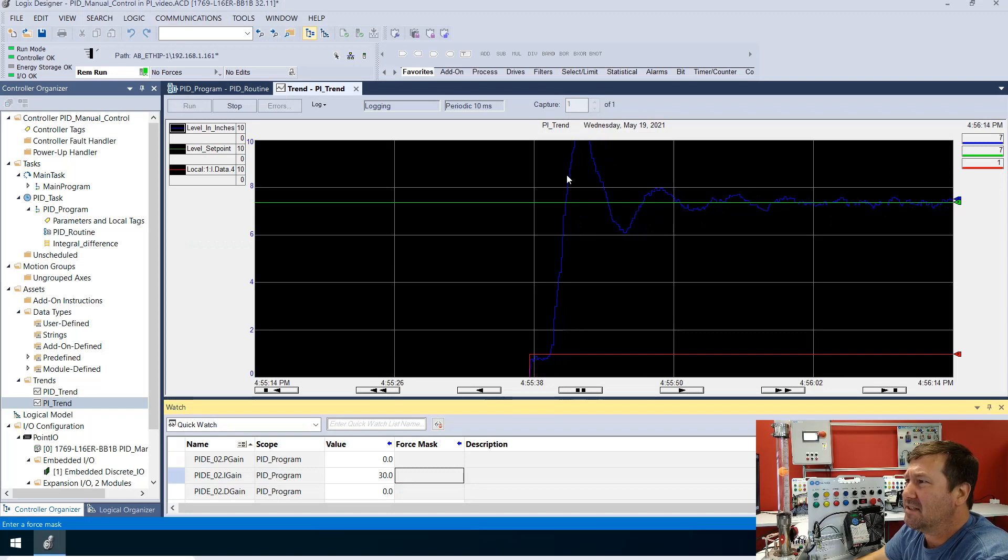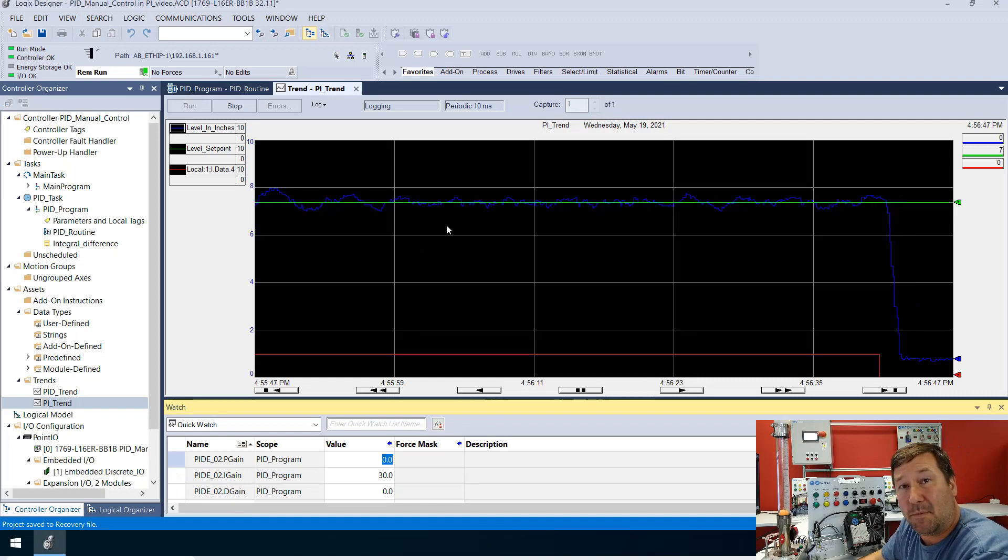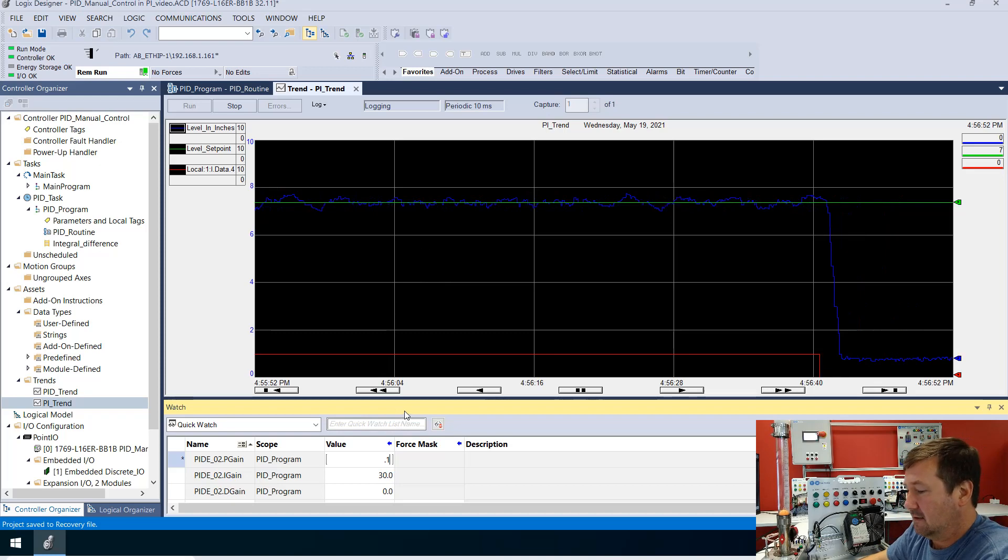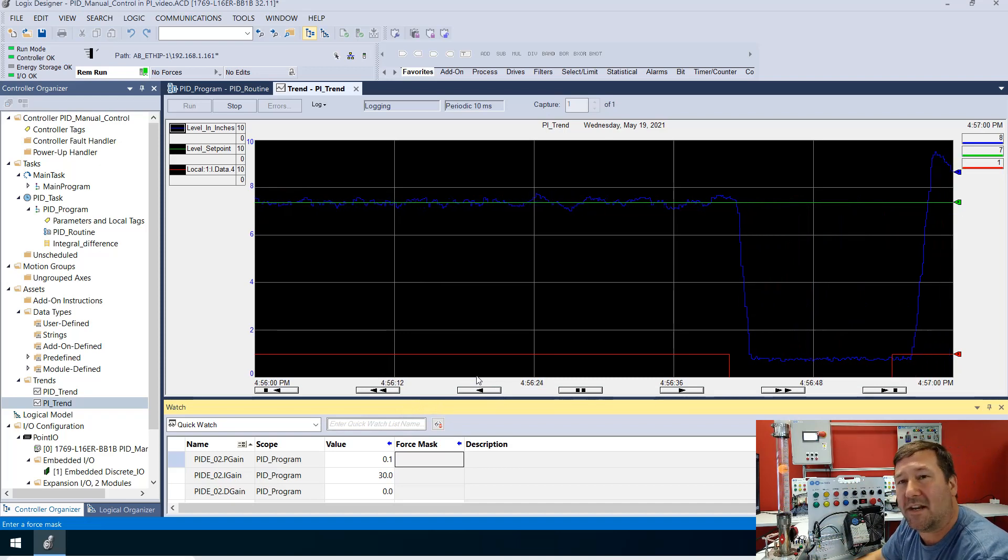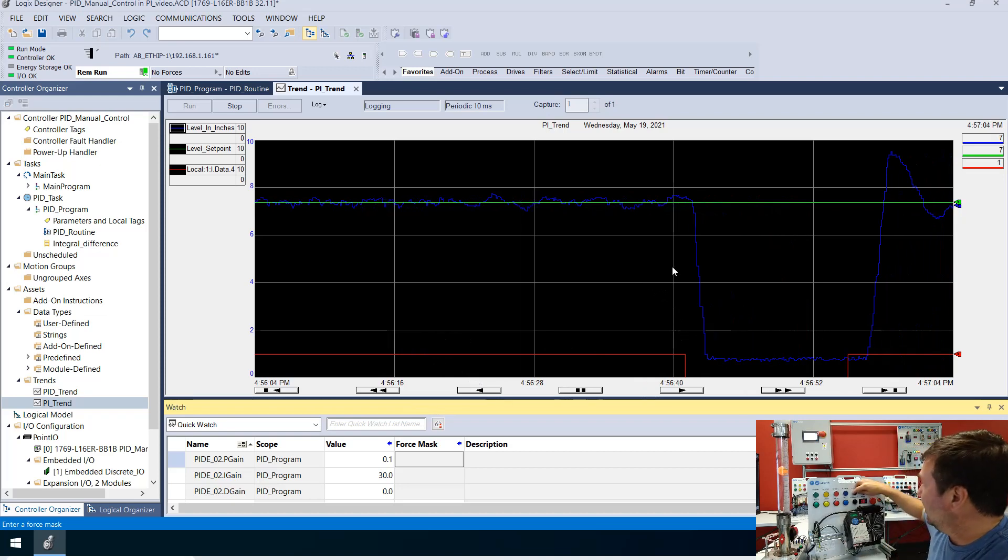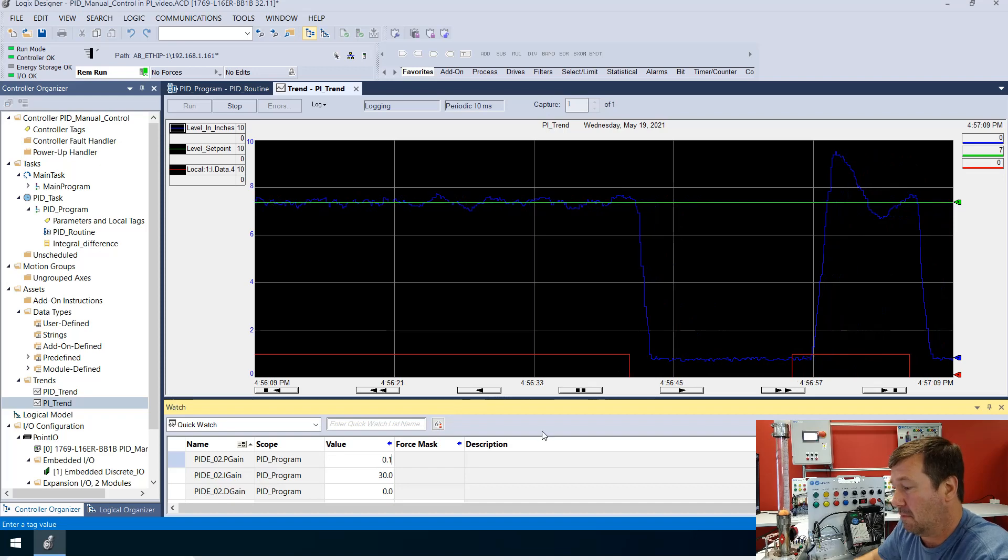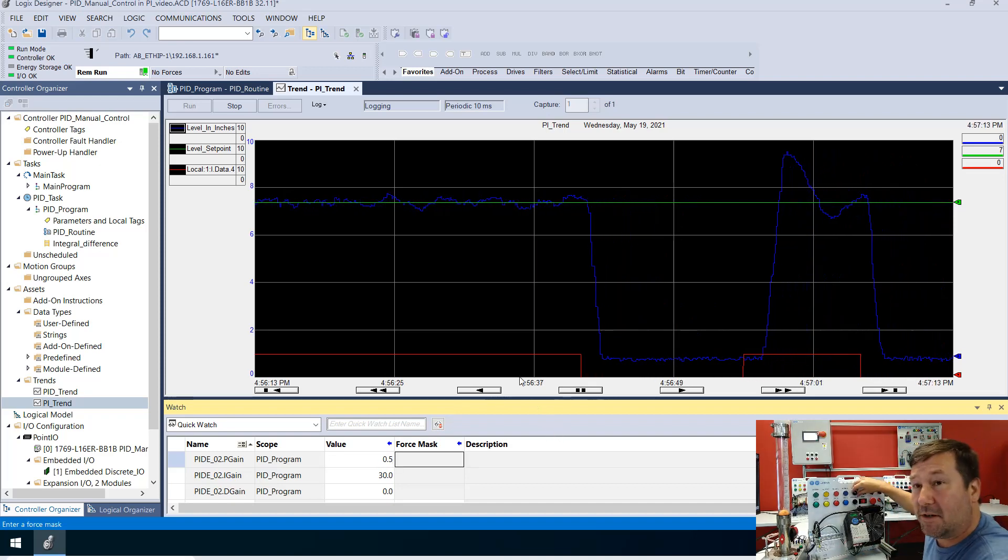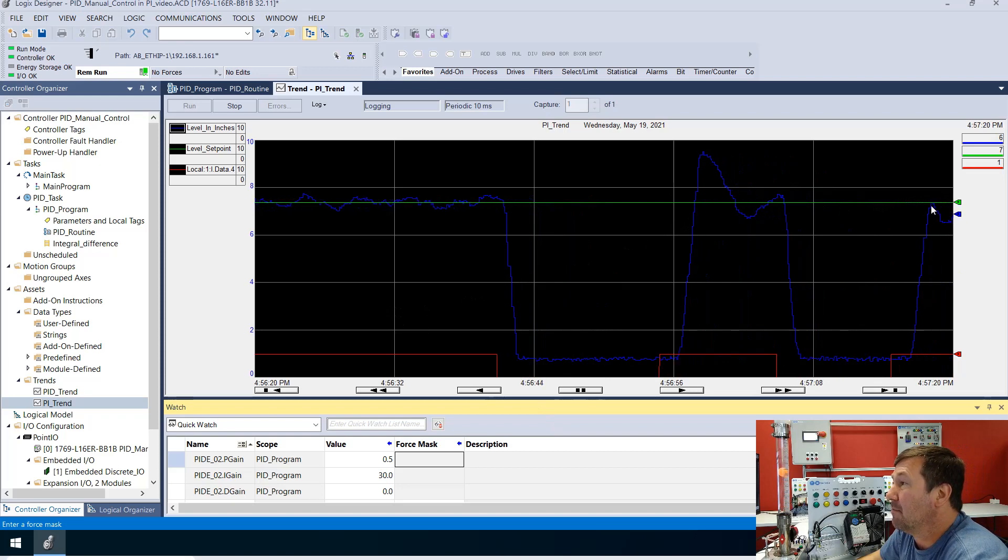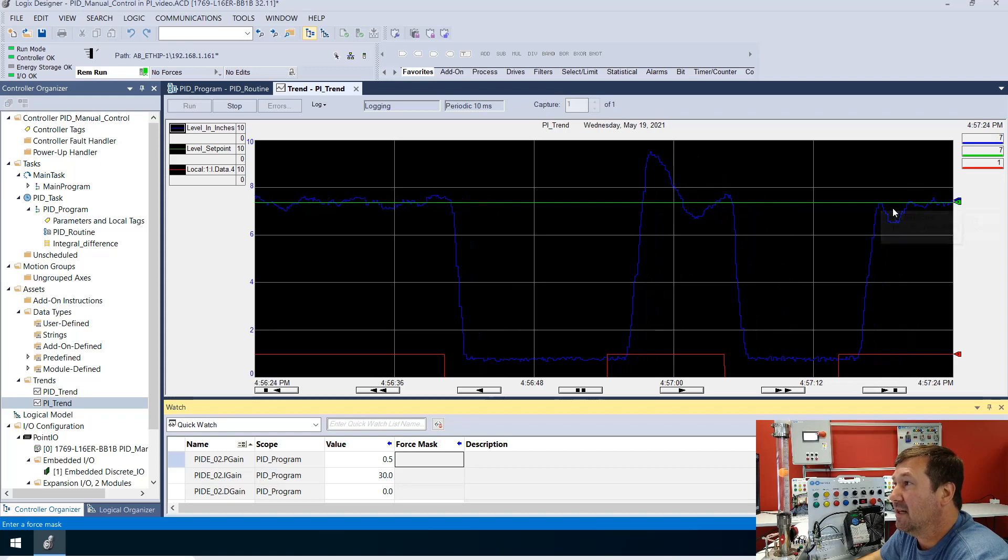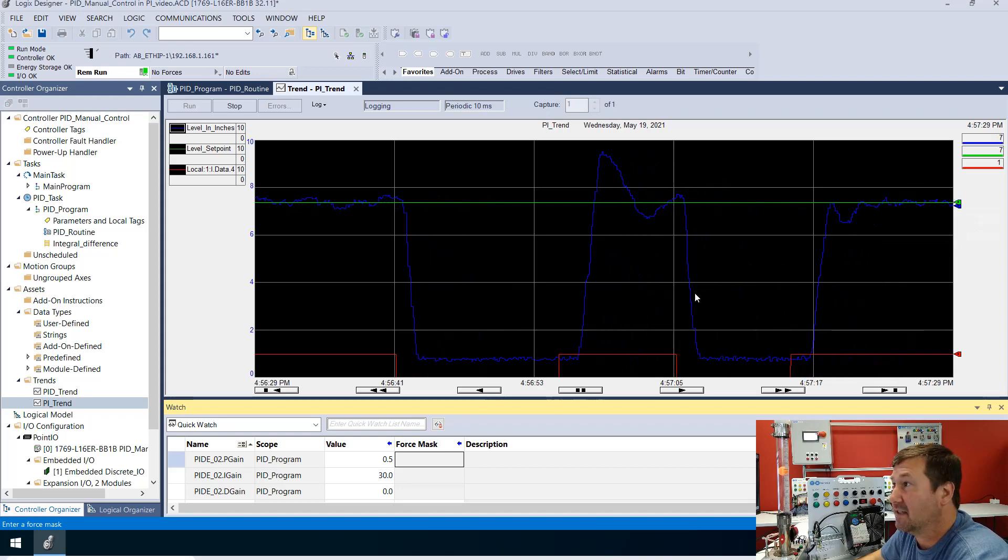Now, this is a horribly tuned PID. But honestly, for a lot of applications, that would probably work just fine. But now let's see what we could do with it using the proportional control. Because mainly what we saw here is that it shot up way too much. Well, we can use the proportional to actually kind of stop that action from happening. So I'm going to put a proportional in of, let's just start with 0.1. And now we'll turn it on. All right, we still got an overshoot, but I should have taken a picture of the last one so you could see the difference. So really quickly, I'm going to change that 0.1 on the proportional to 0.5. And now we're going to switch switch one. And you see there was minimal overshoot. Now we did have some dip here afterwards, but this second one looks much better than this first one.